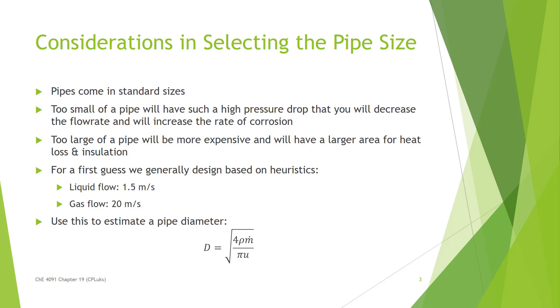What are the considerations you need to think about when selecting the proper pipe size? First, it's really important to know that pipes come in standard sizes — this is not something you're going to custom design. If you choose too small of a pipe, you're going to end up with high pressure drops, which will decrease your flow rate and also increase the rate of corrosion, which is particularly hazardous if you have dangerous chemicals in those pipes.